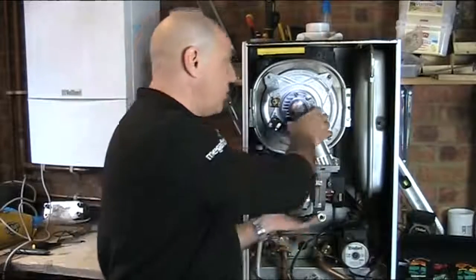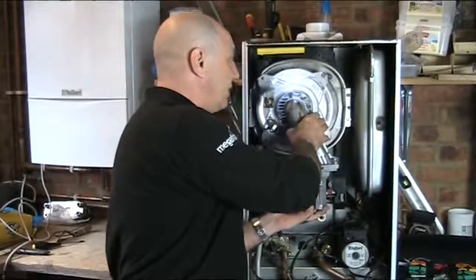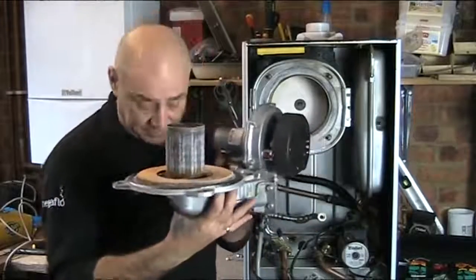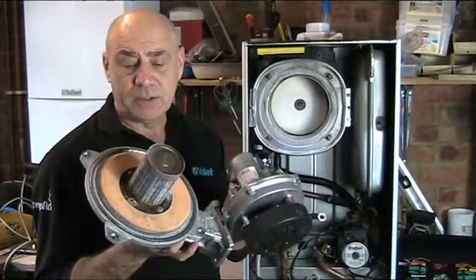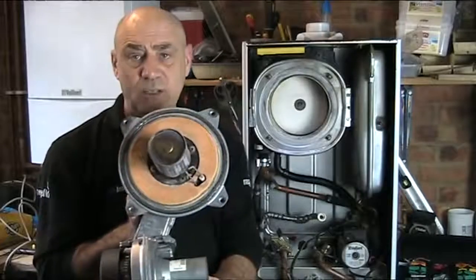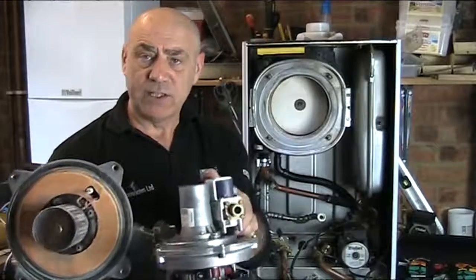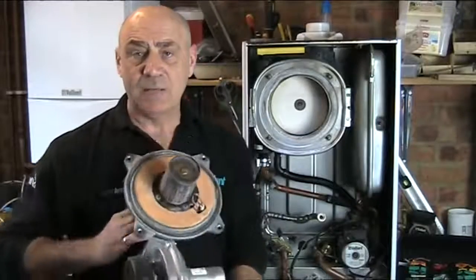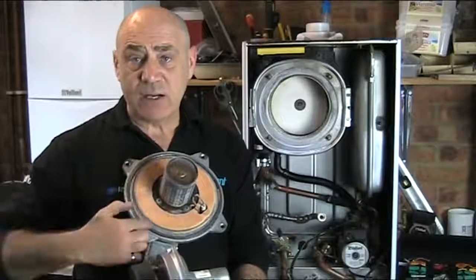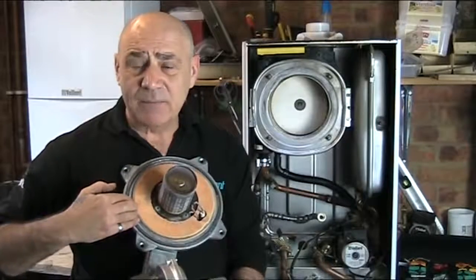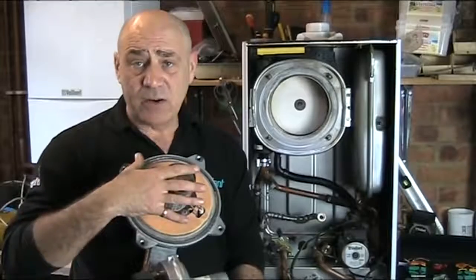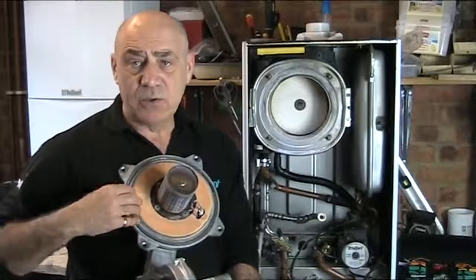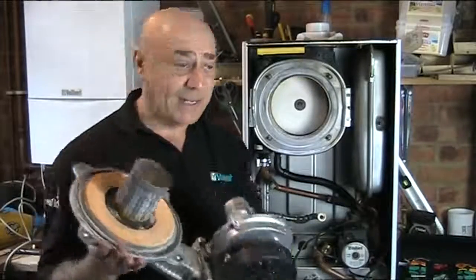So first thing we'll do for the gas side of things is we will remove the burner. Okay, now this will need cleaning. We will also service the ignition system, and more importantly this graphite seal will be replaced. So we'll service all the burner area, replace the seal, and then when we're finished this will go back in.